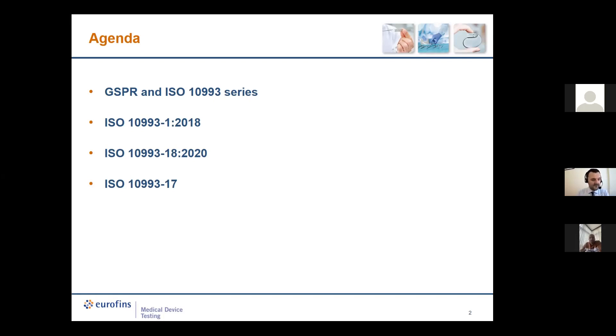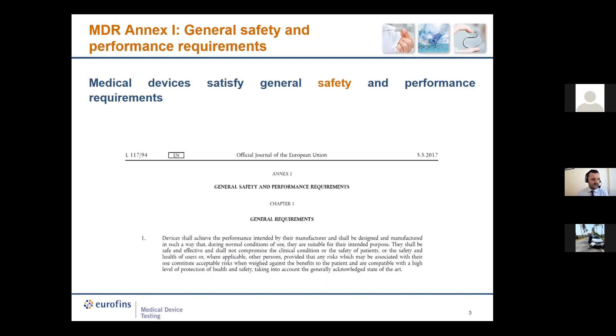ISO 10993-17 is under deep revision. Let's start with the MDR. You are familiar with Annex I, where the general safety and performance requirements are listed. Those requirements are general — we are in the so-called new approach — and they do not provide technicalities on how to comply with them. It's here that we find the need to assess biocompatibility and perform a biological evaluation. The MDR says that particular attention shall be paid to the choice of materials and substances used in a medical device, particularly regarding toxicity.